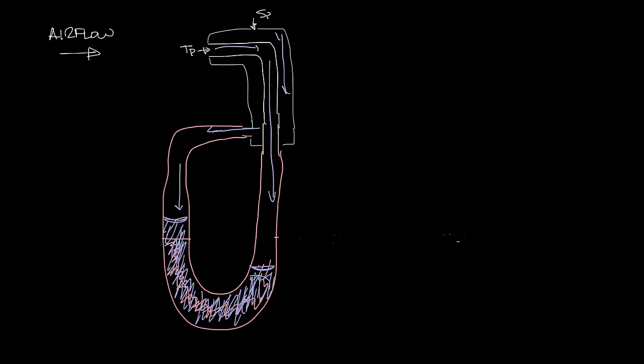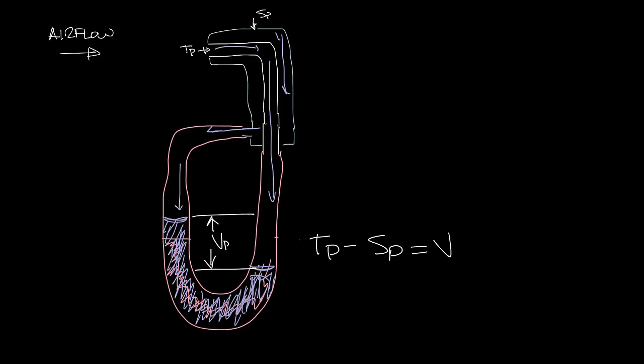So now you see that the manometer has two different levels, and the difference between this top and the bottom level of the liquid is the velocity pressure. Because if you remember, total pressure minus static pressure is velocity pressure.